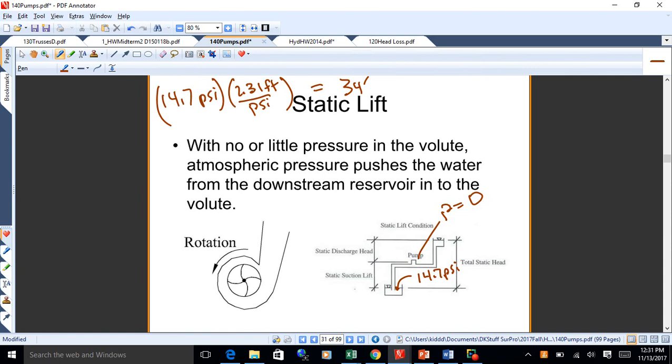You just can't do it because all you're doing with a pump is creating a vacuum. That's all you can do. So you can't lift water any higher than 34 feet. You can push water more than 34 feet, but you can't lift it. It doesn't matter what you do. If you had 134 feet, then you have to get another pump for that, and then lift it again. Well, really, you'd be more pushing the water with the first pump. That would be the right way to word that, I think.